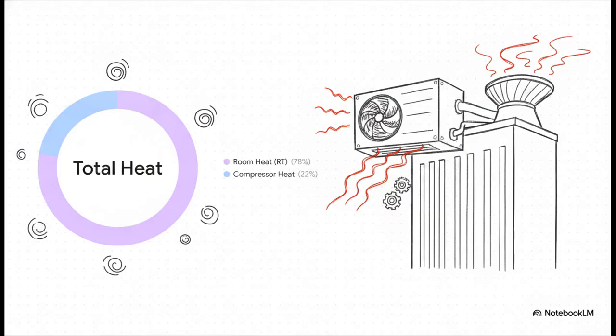And here is the answer to our mystery. The total heat thrown outside isn't just the room heat. As you can see, the biggest chunk is definitely the room heat removed, RT, but check out that second slice, compressor motor heat. You see, to pump that refrigerant around the building, the cooling machine works incredibly hard. That compressor motor uses a massive amount of electricity, and thanks to mechanical friction, it generates its own heat. The act of cooling the building literally creates extra heat. Because of this, the exhaust load pushed up to the roof is actually 30 to 40% larger than the heat we pulled out of the room.